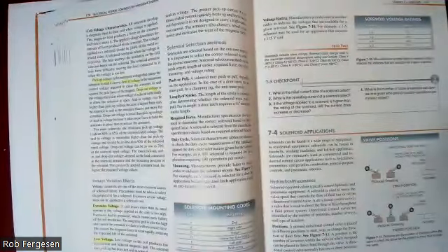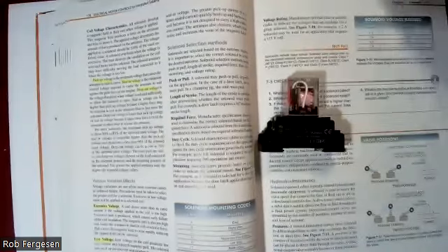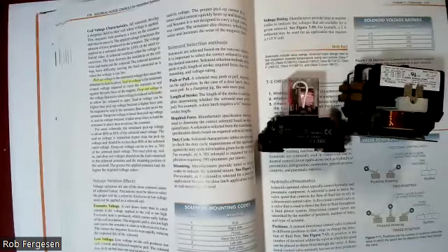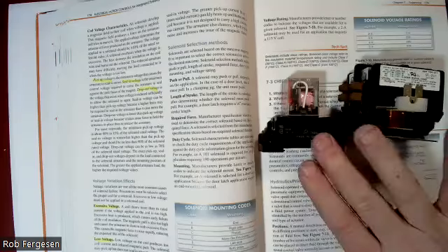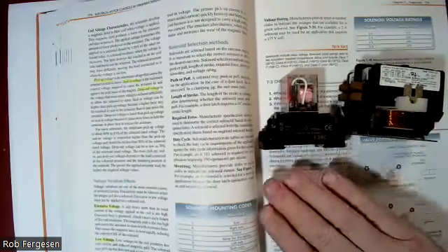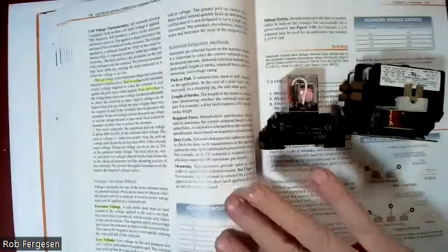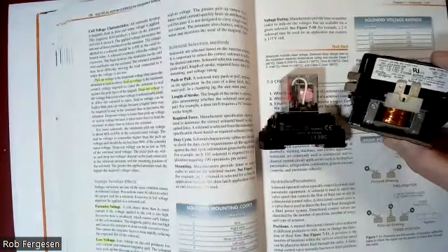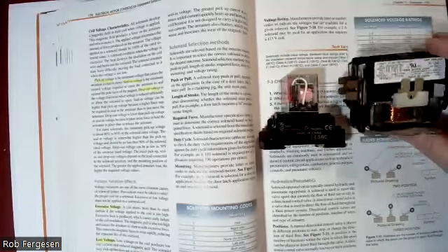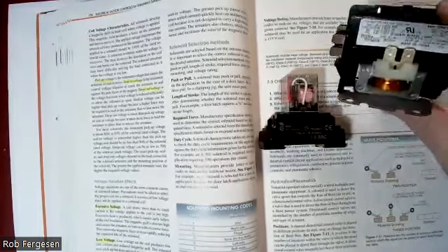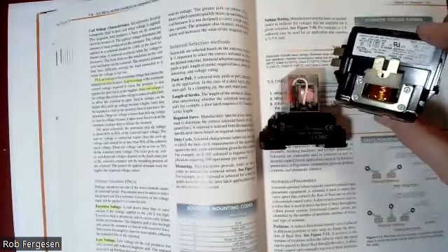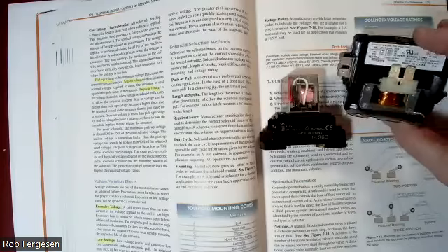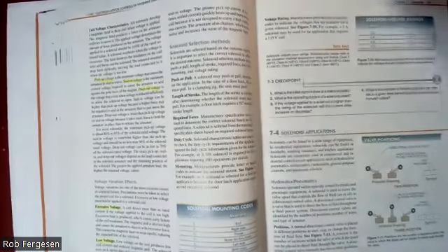In general, for industrial controls where I've got relays like this or contactors like this, my voltage tends to run pretty consistent. You know, it's 110 volts or 220 volts or 24 volts DC throughout my system. But every once in a while, you'll run into an application where, because of the way this is wired or the plant you put this in, it's running right at the low end of its voltage range. And if it does that, then knowing that your contactor has a pickup voltage or dropout voltage at a certain point is very, very important, because then it helps you diagnose problems.